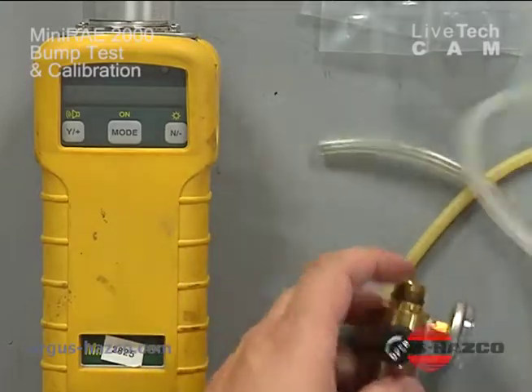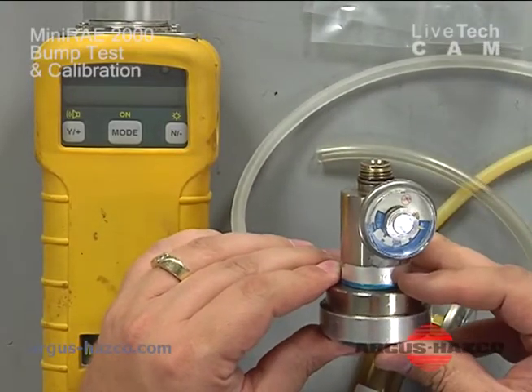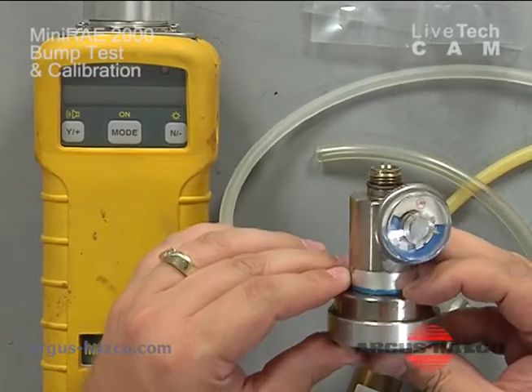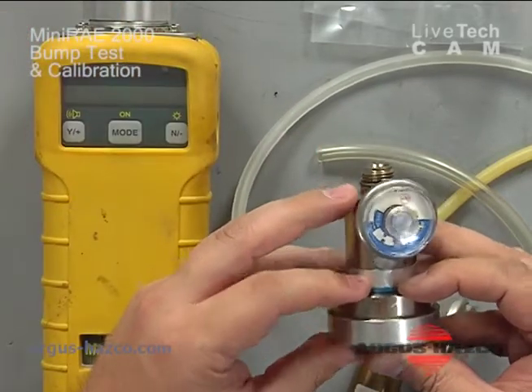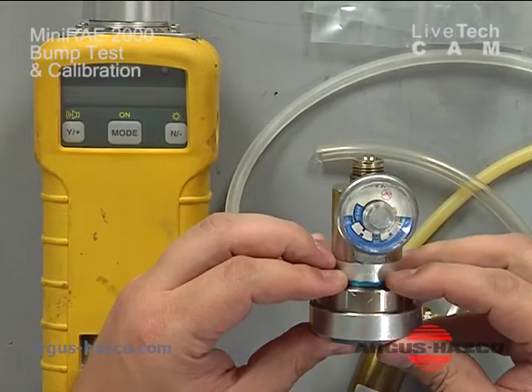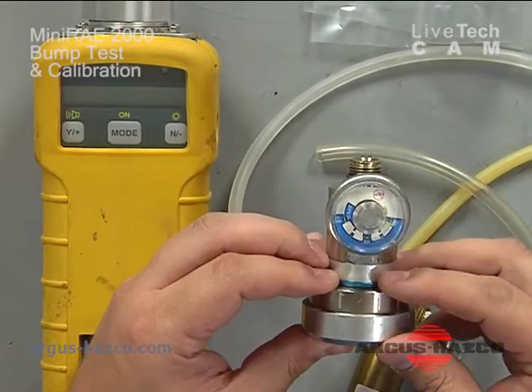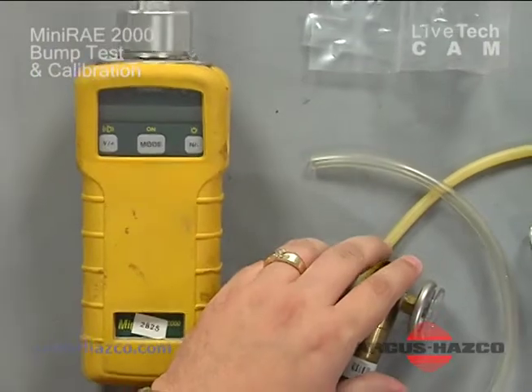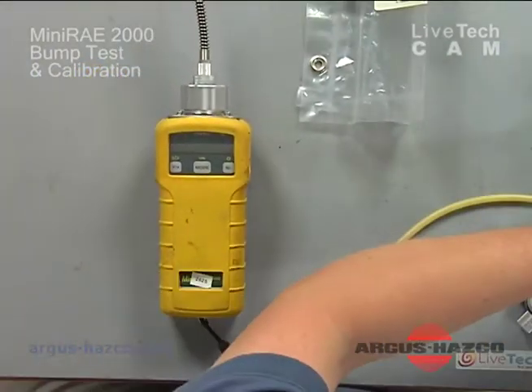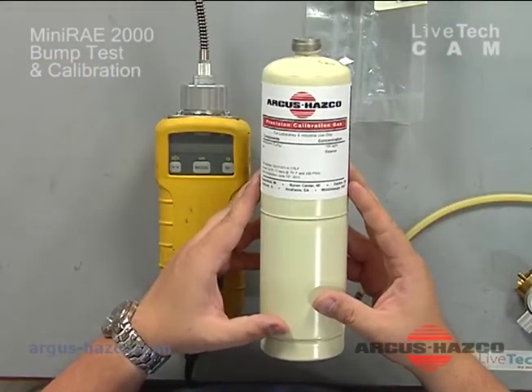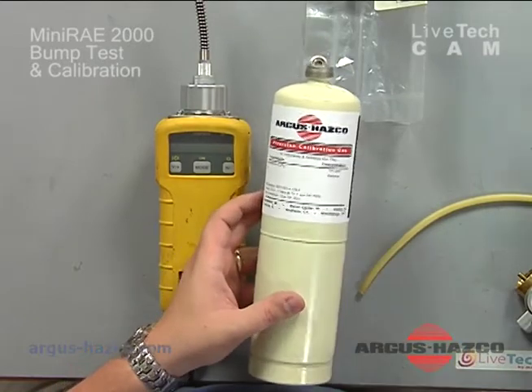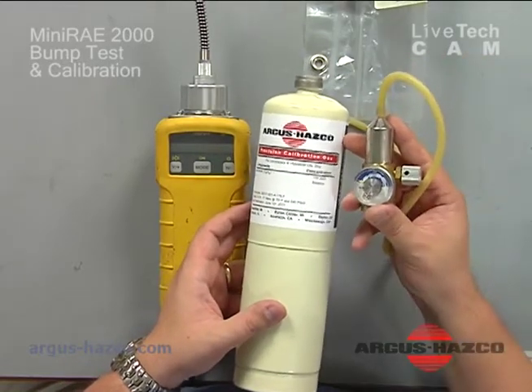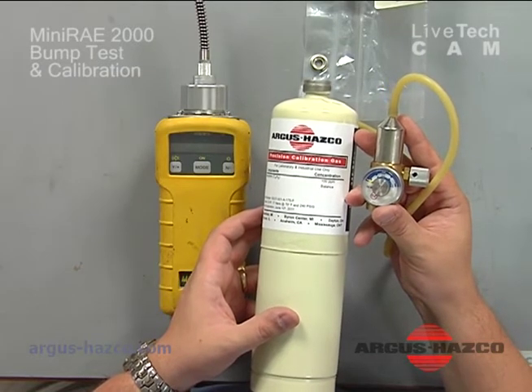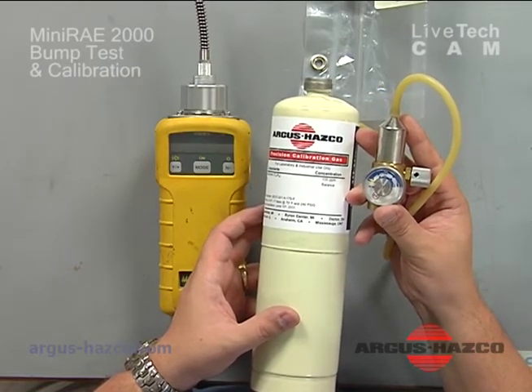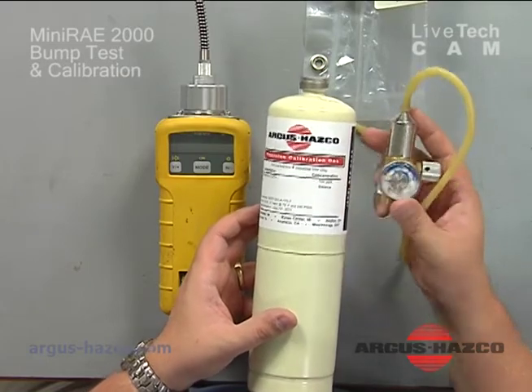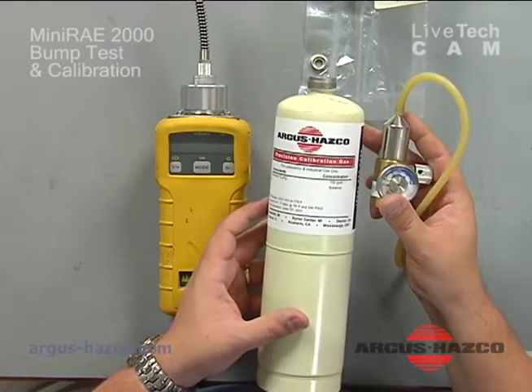Another type of regulator is called a demand flow regulator. This will not work until there's a sample drawn out of the regulator, which opens the valve, and it will match the sample that the pump is pulling and allow the gas to come out of the cylinder. A cylinder that we provide with a rental is a 17 or 34 liter cylinder of isobutylene that uses the female regulator at a preset rate of 0.5 liters per minute, which is recommended by RAE Systems for calibration to match the pump flow. So we provide that with a rental, and that's what we're going to use today.